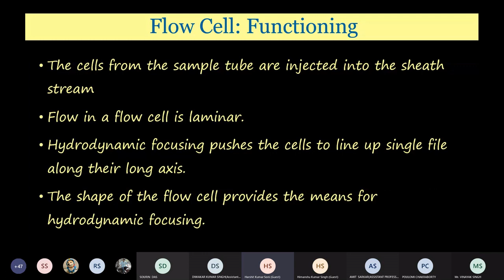We have both the buffer system, the sheath fluid, as well as the medium in which we are making the cell suspension. These two are in flow, which means they are in a dynamic condition, and this creates the focus. So hydrodynamic focusing pushes the cells and lines them up into a single file along the long axis, so only a single cell will go through. The shape of the flow cell provides the means for hydrodynamic focusing, so hydrodynamic focusing is supported by the shape of the flow cell.